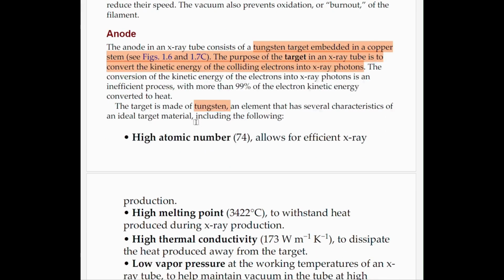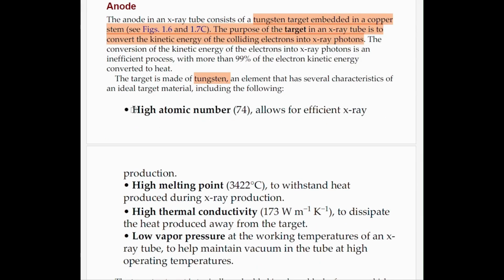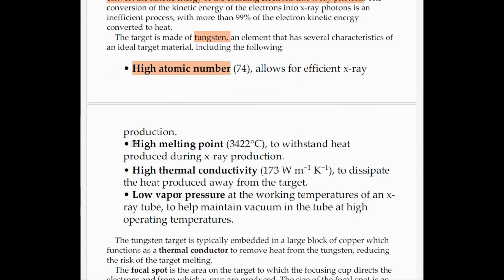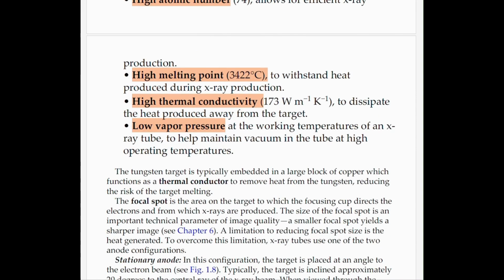Why is it made of tungsten? You have to mention these points. High atomic number allows for efficient X-ray production, high melting point, that is 3422 degrees Celsius, to withstand heat, high thermal conductivity, and low vapor pressure. So why is tungsten selected? Because of its high atomic number, high melting point, high thermal conductivity, and low vapor pressure at the working temperature of an X-ray tube, to help maintain a vacuum in the tube at high operating temperatures. Hence, a low vapor pressure is required.